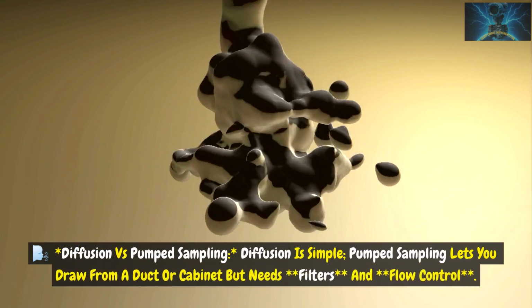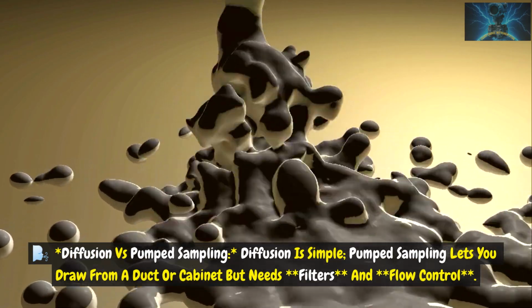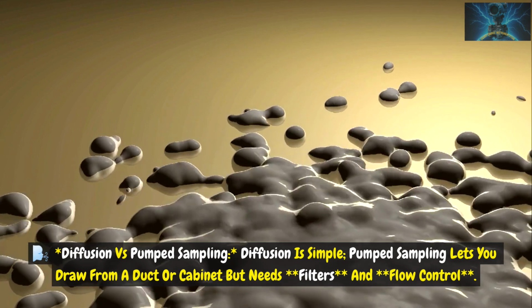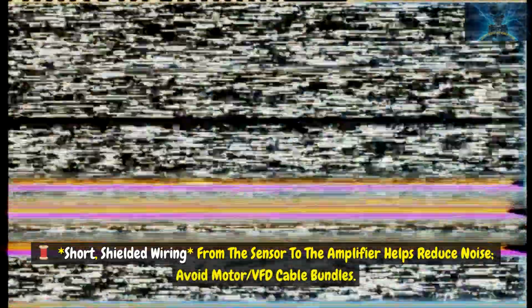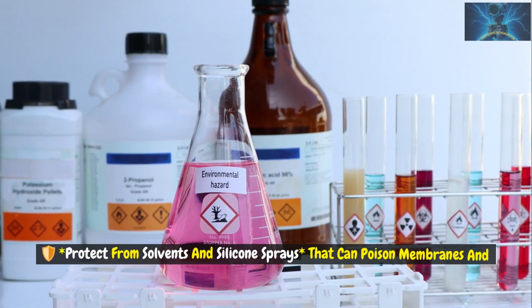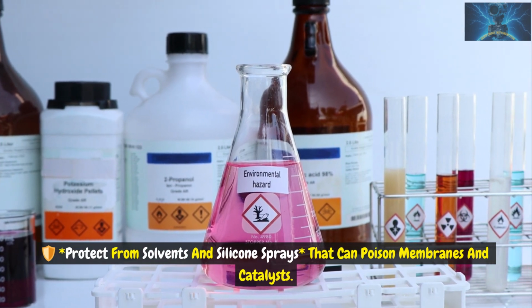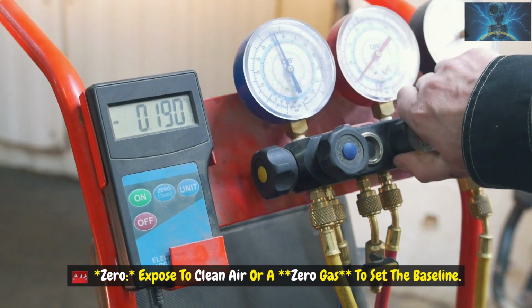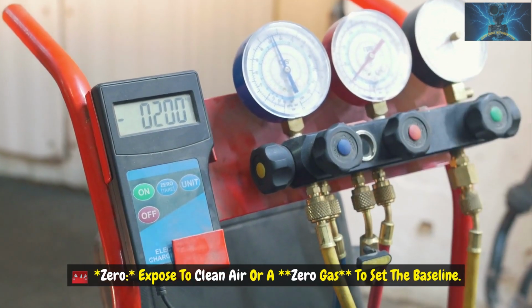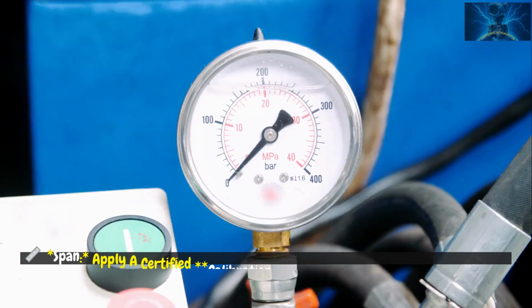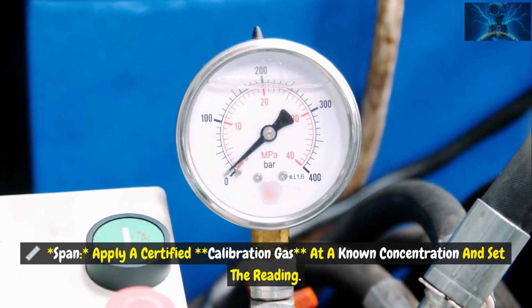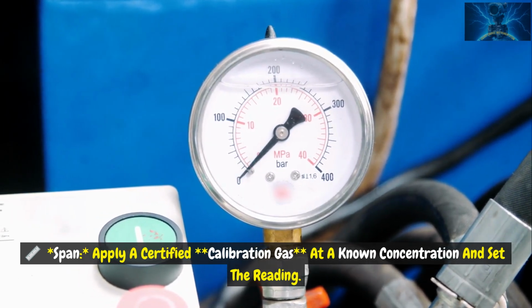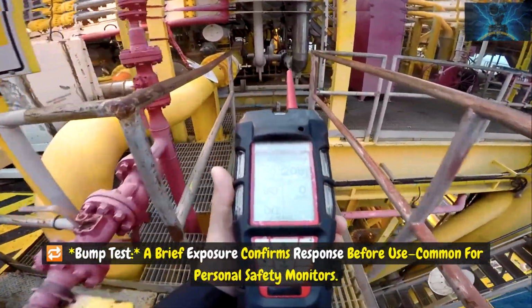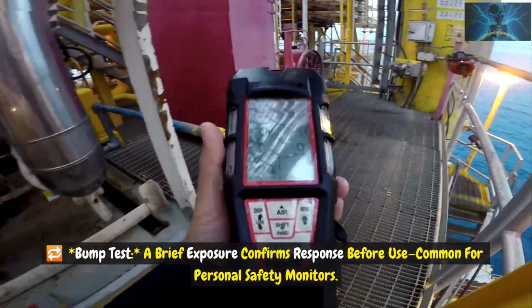Diffusion versus pumped sampling. Diffusion is simple. Pumped sampling lets you draw from a duct or cabinet but needs filters and flow control. Short, shielded wiring from the sensor to the amplifier helps reduce noise; avoid motor VFD cable bundles. Protect from solvents and silicone sprays that can poison membranes and catalysts. Calibration and bump testing. Zero: expose to clean air or a zero gas to set the baseline. Span: apply a certified calibration gas at a known concentration and set the reading. Bump test: a brief exposure confirms response before use, common for personal safety monitors.